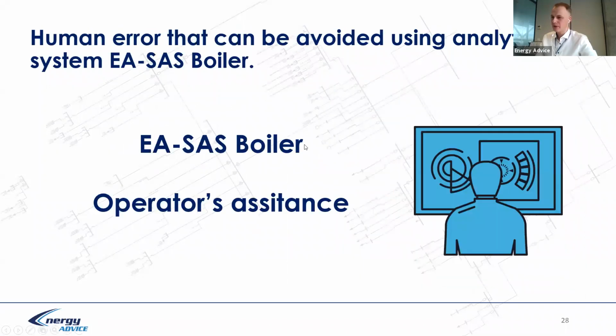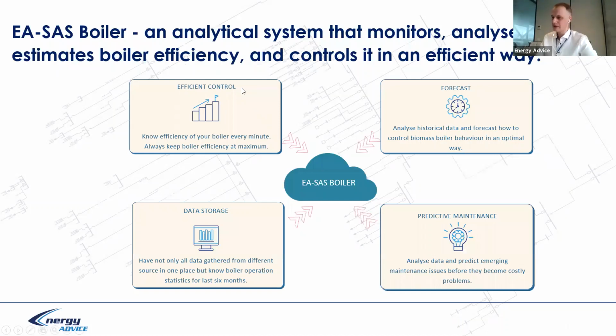So what we are telling is that it is boiler operator assistance. In fact, in some countries, boilers are running without operators. In some countries, boilers are running with operators. Smaller boilers are running without operators. Higher capacity boilers are probably running with operators. It depends on the country. However, it would be assistance for the human, for efficiency control every minute, and keep the boiler at the maximum efficiency that is possible at that time, according to the situation of the boiler, according to when previous maintenance activities were done.